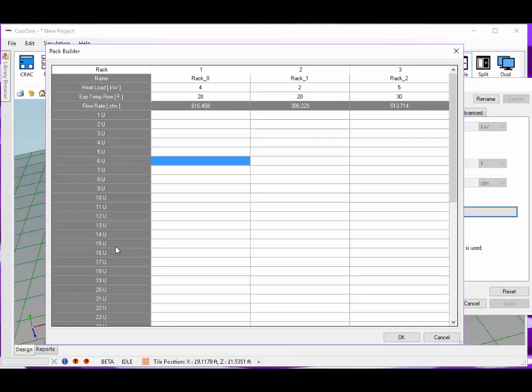We did it this way just so we could vary the height of the racks and not have this interface change very much. So it was a constraint building the user interface that kept it this way. These are inverted. It hasn't been too much of a trouble for people, but keep it in mind. So let's say here in rack 0 that 4 kW is fine, but it's really not distributed evenly across the front of the rack. It's really right here.